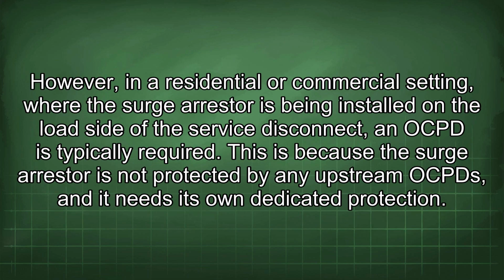However, in a residential or commercial setting, where the surge arrestor is being installed on the load side of the service disconnect, an OCPD is typically required. This is because the surge arrestor is not protected by any upstream OCPDs, and it needs its own dedicated protection.